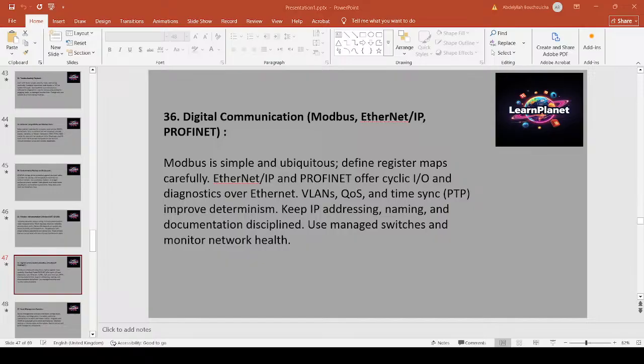Modbus is simple and widely supported. Define register maps and scaling carefully to avoid confusion. EtherNet/IP and Profinet bring richer diagnostics and cyclic I/O over Ethernet and are suited for faster control requirements. Use VLANs, QoS, and time synchronization with PTP or NTP where determinism matters. Document IP addressing and device names, and use managed switches with monitoring and redundancy. Example: use Modbus RTU for older analyzers into a gateway and EtherNet/IP for modern I/O racks feeding the PLC with explicit produced data exchange.